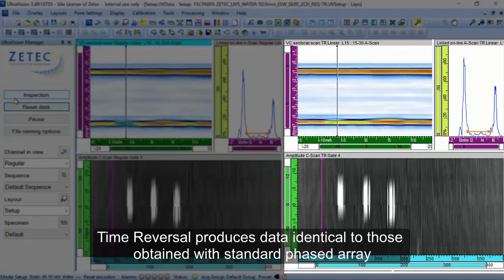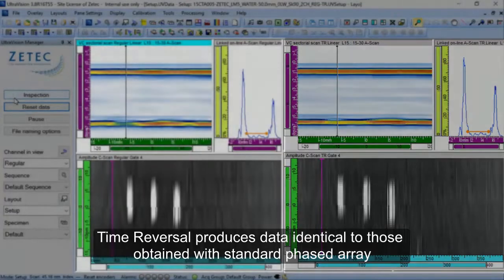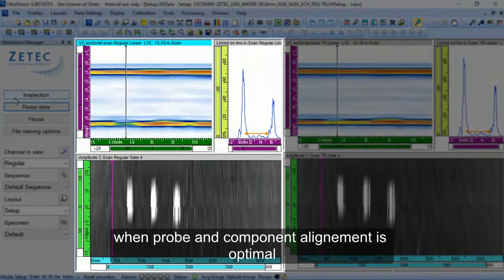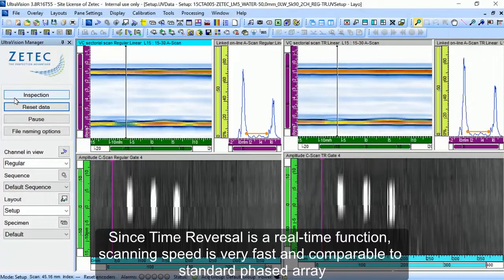Time reversal produces data identical to those obtained with standard phased array when probe and component alignment is optimal. Since time reversal is a real-time function, the scanning speed is very fast and comparable to standard phased array.